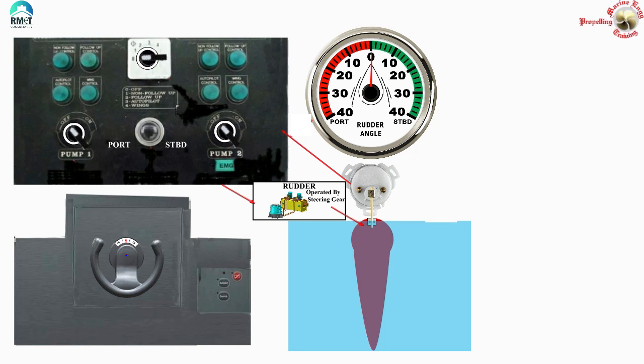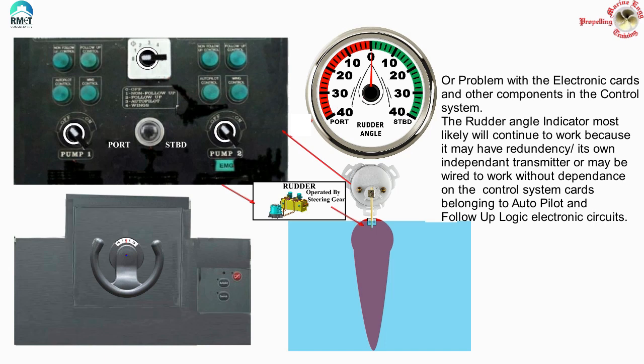When do we use non-follow-up mode? One of the main reasons is when we have a disruption of the signal flow from the rudder angle transmitter to the system. If there is an electrical problem or the rudder angle transmitter is not able to send the feedback signal to the system, then we have no choice but to switch to non-follow-up mode.